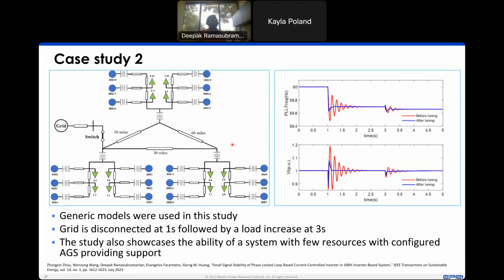Now, an interesting point here is that when we were doing this work and we spoke to the OEM and brought about these results, one of the reactions from one of the OEMs was, yes, we did look into this earlier for a distribution system concept, but at that time we didn't look into it further because there were concerns about unintentional islanding causing an issue and a system running as usual.